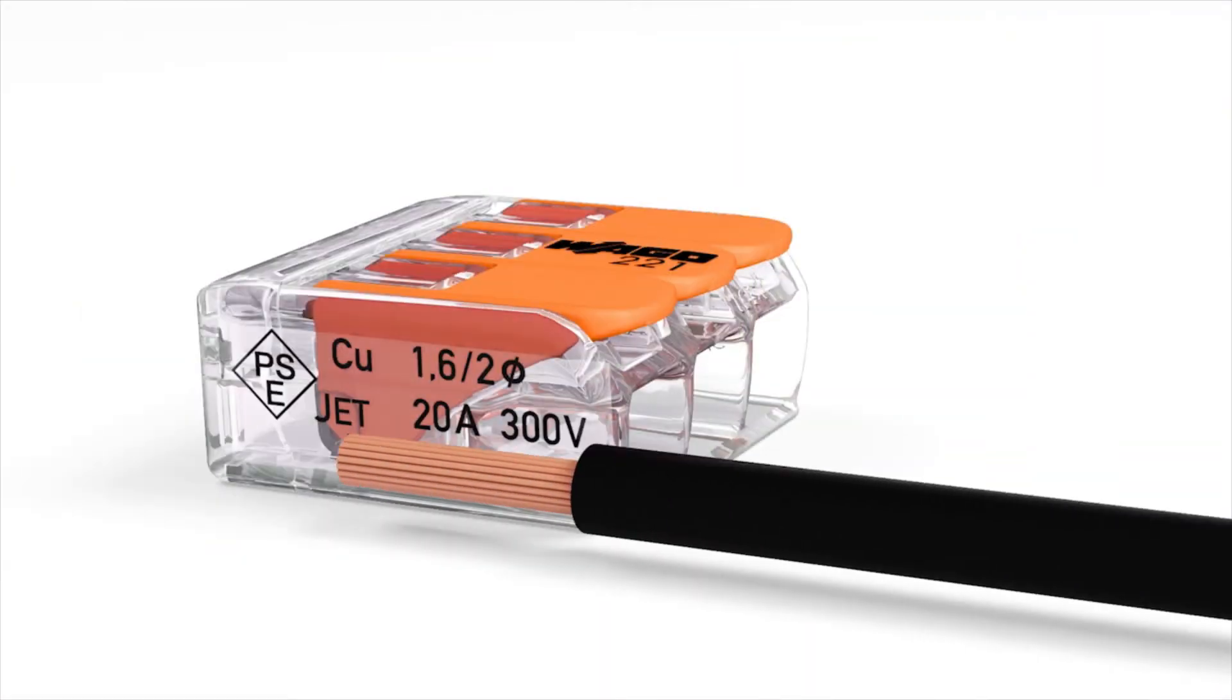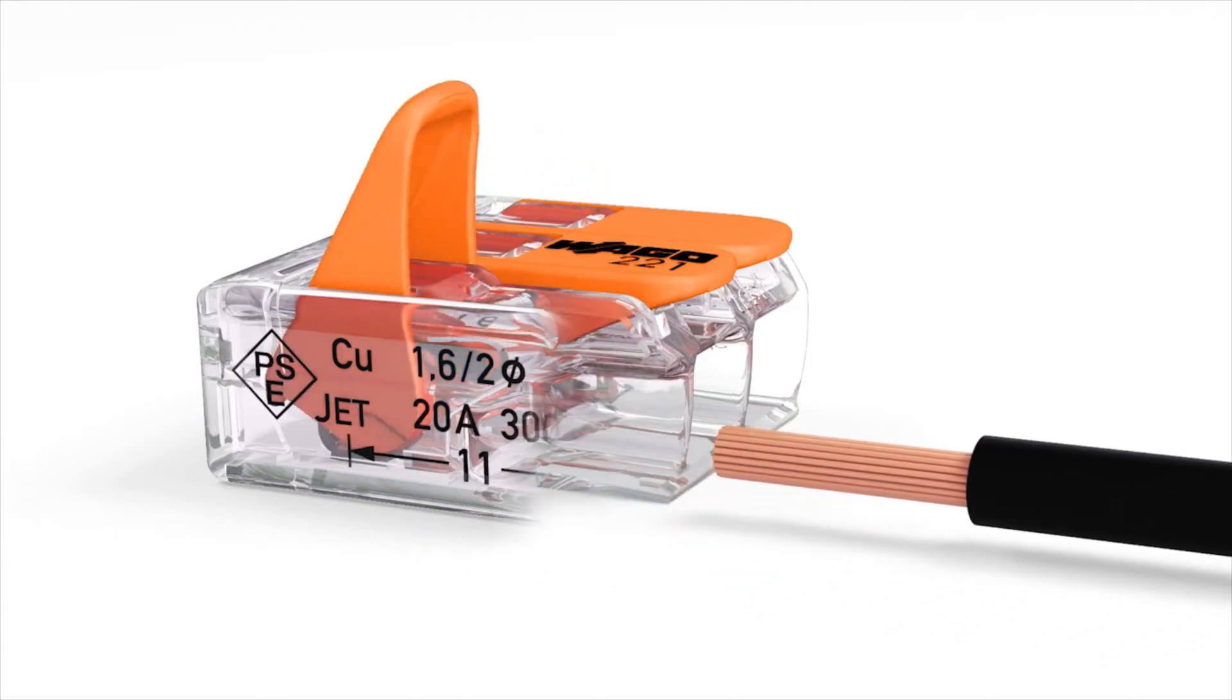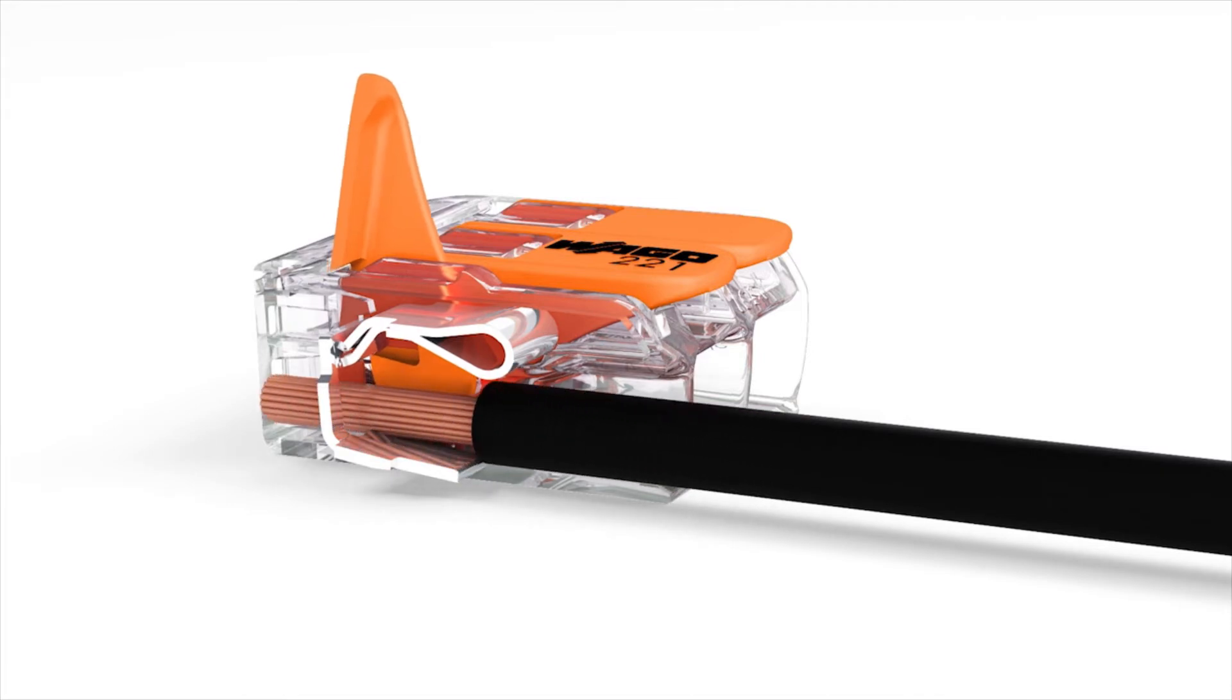Strip the conductor according to the strip length guide printed on the side of the connector housing. Open the clamping unit via the easy-to-use orange lever. Insert the stripped conductor, then lower the lever to close the clamp.